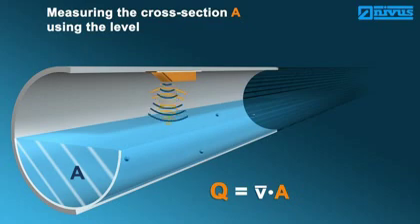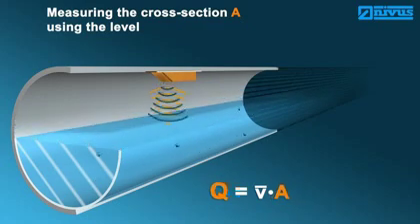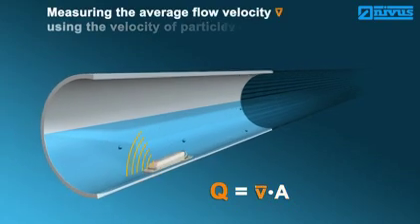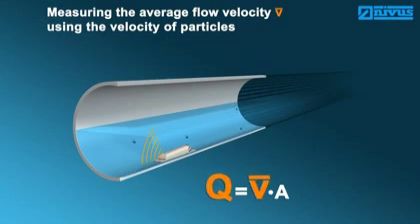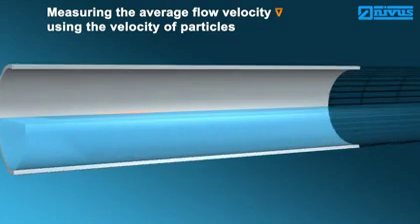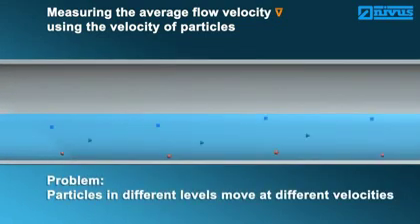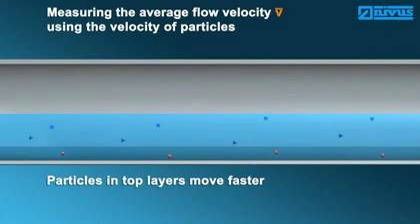The flow velocity is detected by measuring the particle velocity. Most media, particularly wastewater, contain dirt particles or gas bubbles moving with the same velocity as the medium. The velocity of the particles is measured using ultrasound. As soon as the velocity changes, the flow normally changes as well. The main difficulty while detecting the average flow velocity is that there are varying velocities prevailing at varying levels. The medium and hence the particles normally flow slower at low levels than at higher levels.